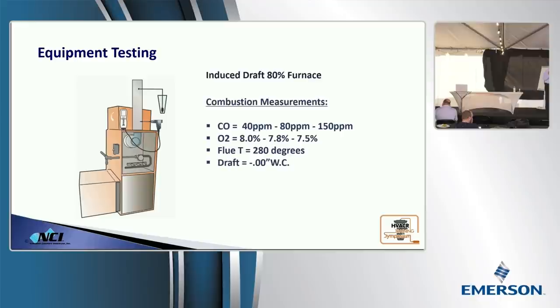Now, what's interesting with that little Dwyer draft gauge is it's negative pressure only. So you could actually have positive pressure in that flue, and it will force that little white ball down to the bottom, so you won't see that. So it's kind of interesting there. If you take one set of readings, can you pick up this pattern? You'll miss it every single time. Guys, this is the most dangerous type of operation on fuel-fired equipment that we miss if we take one single set of readings. We miss this every time. You need multiple sets of readings.